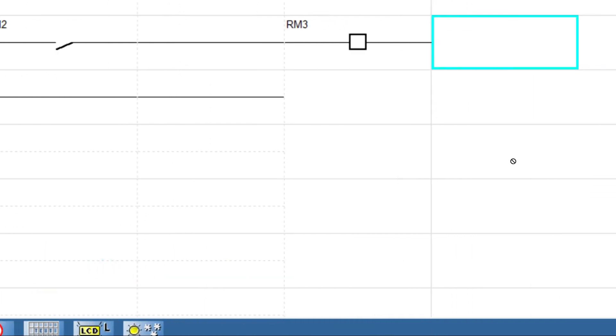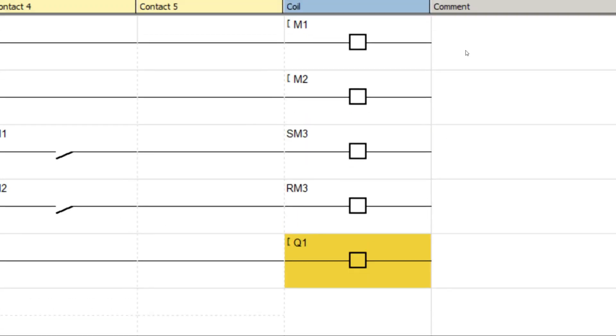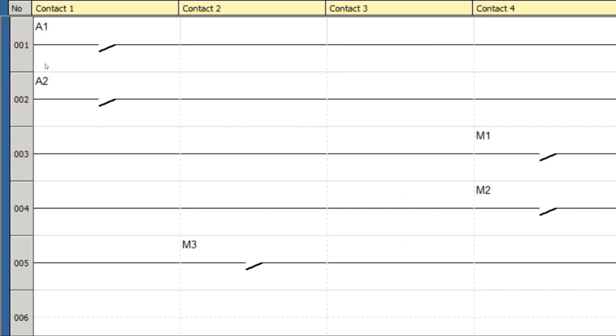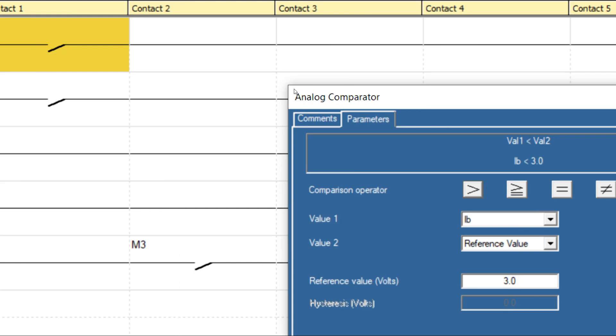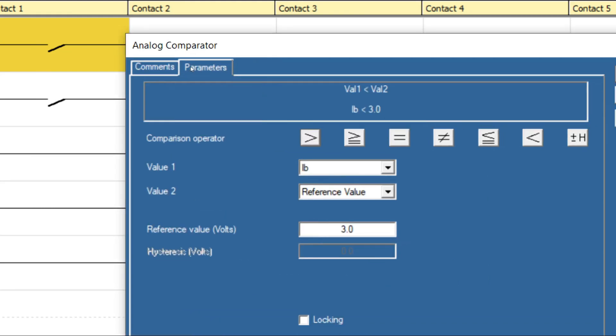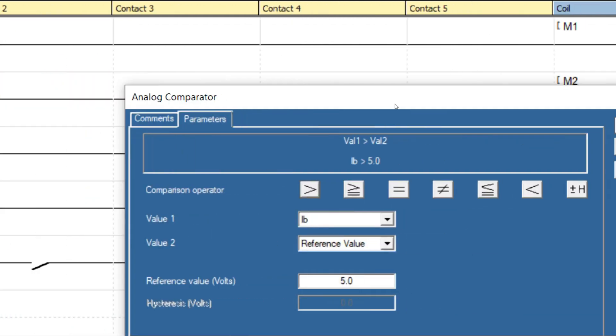Digital output Q1. Now we made logic like this: if the analog value is below 3 bar or 3 volt, the pump should start till 5 bar. If the pressure reaches 5 bar, the pump should stop. Again, pump will start if the voltage - means the pressure - drops below 3 bar.